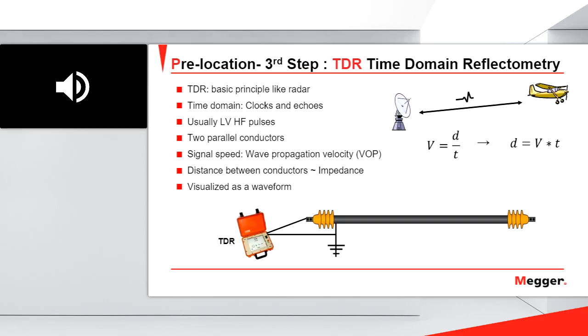So in this picture that we have here, the only two changes of impedance are, first, the change of impedance at the beginning of my cable, because there is a change of impedance between the test leads of my TDR and the medium voltage cable. Then we will not see any other change of impedance, because there is not a change in the resistance of the cable. And the second change of impedance will be at the end of the cable. Those are the only two changes of impedance in this picture, at the beginning and the end. Okay, so let me explain this in the next slide.